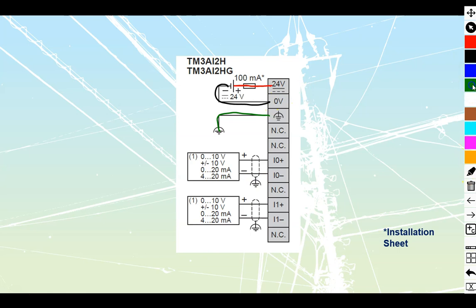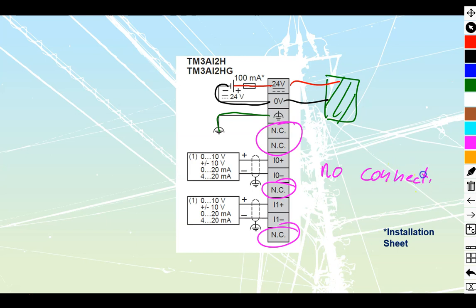This whole top section is really just to power the internal circuit board. It passes through from inside there and powers up the internal circuit board that's doing the sampling. Then we take a look over here, IO zero or input zero, we have a positive and a negative. And then input one, we have a positive and a negative. We also see a lot of these NC, which stands for no connection or not connected. We're not bringing any wires into those ones.